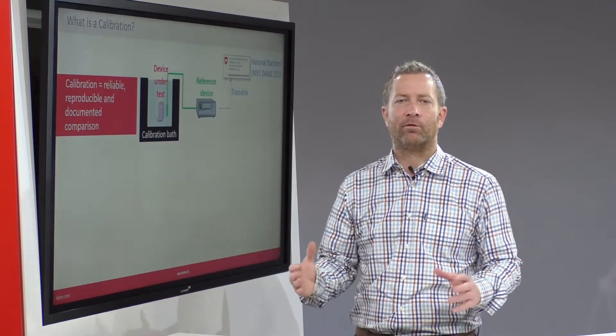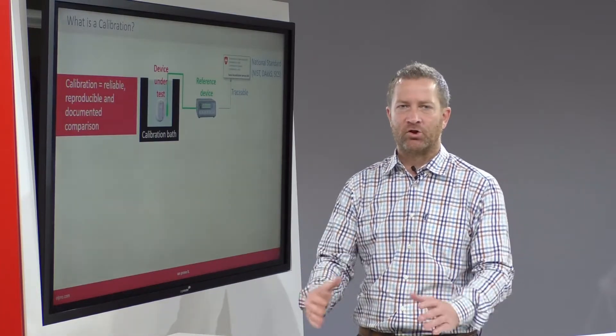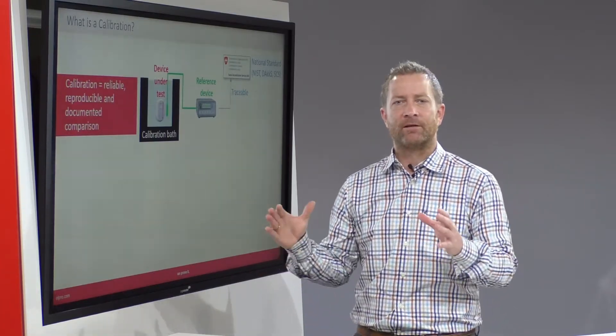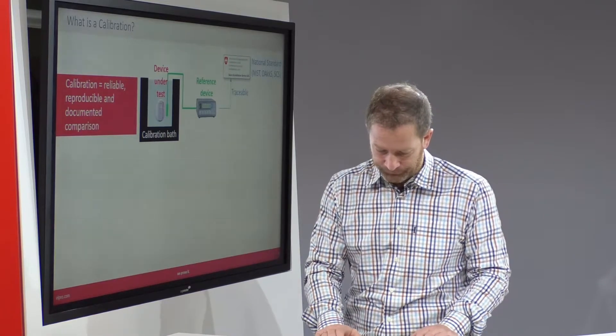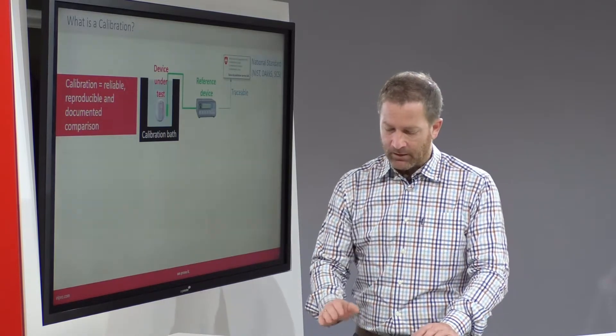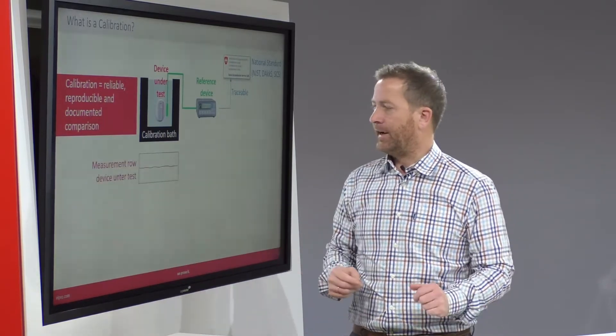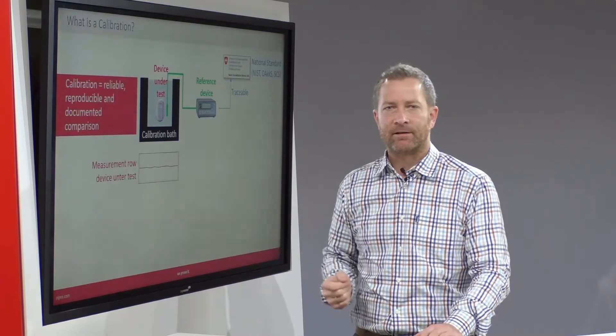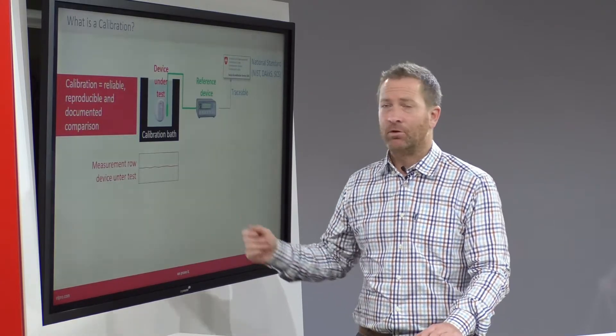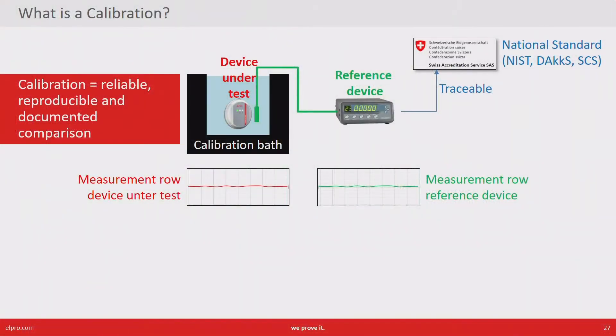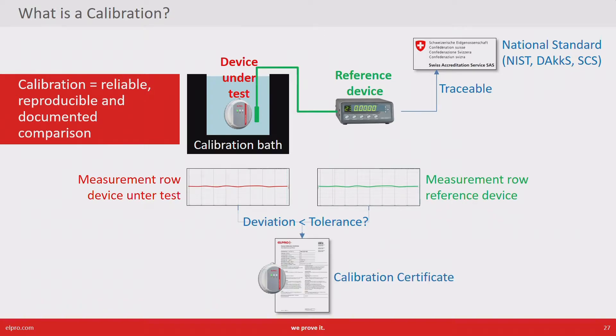A calibration is always performed at one or several temperature points. To perform the calibration we need some sort of device or machine which maintains a stable environment. Afterwards we simply compare the measurement readings of the device under test with those of the reference device, and if the deviation is within the defined tolerance we can issue a calibration certificate.